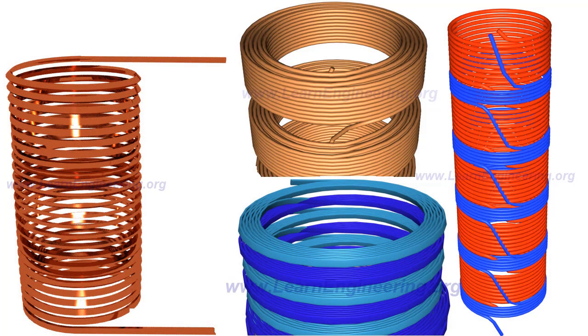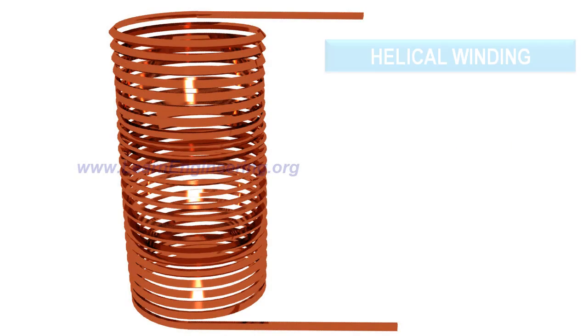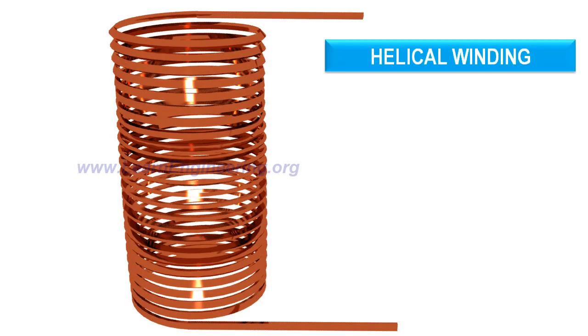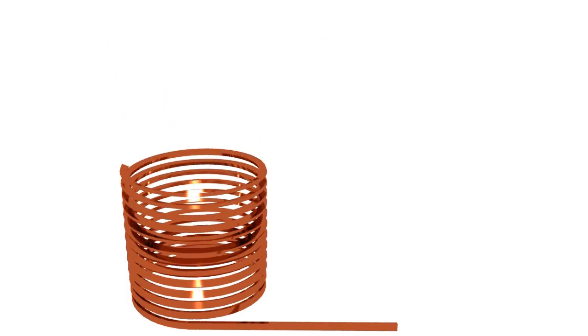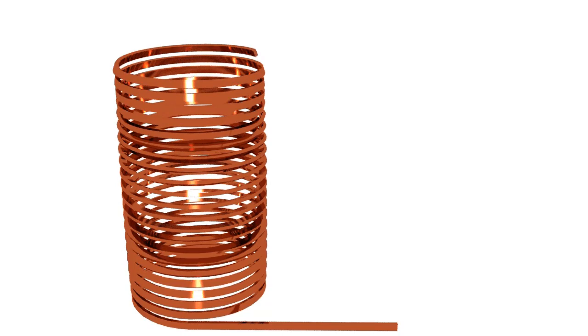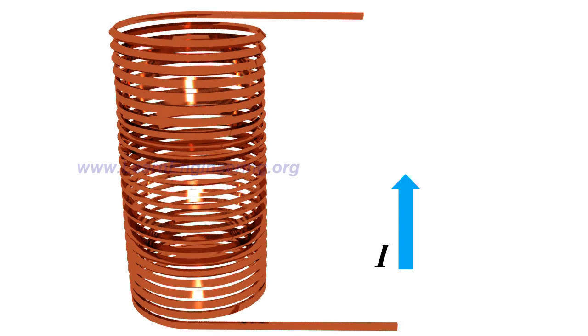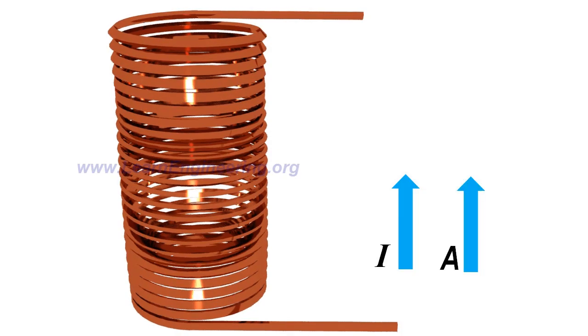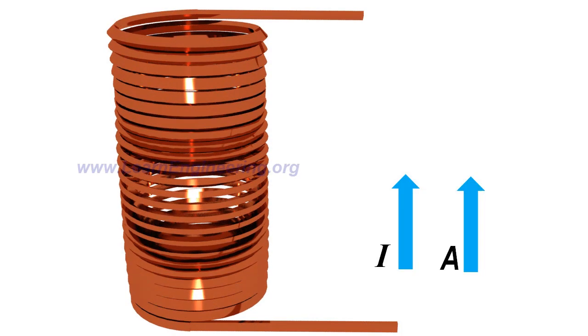One of the most commonly used winding methods is helical type. Helical windings are shaped into a helix and are usually used in low voltage windings. But as the current to be handled becomes larger, the complexity of such windings increases. A large current requires a large cross-sectional area, thus eddy current loss also becomes high.